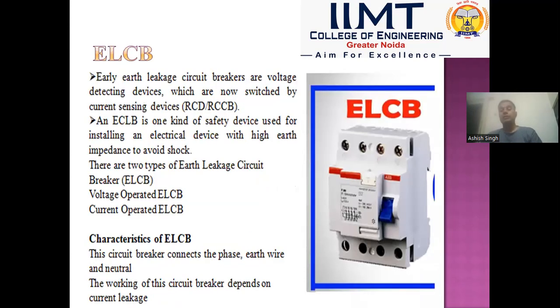The fourth component that is used in LT switchgear is the earth leakage circuit breaker or ELCB. Earth leakage circuit breaker mainly detects leakage current that leaks through earth due to manufacturing defect or insulation failure of the apparatus. Due to the insulation failure or manufacturing defect, current leaks from the current carrying conductor to the outer non-current carrying metallic part. So these devices detect leakage current, and after detecting it, ELCB operates.